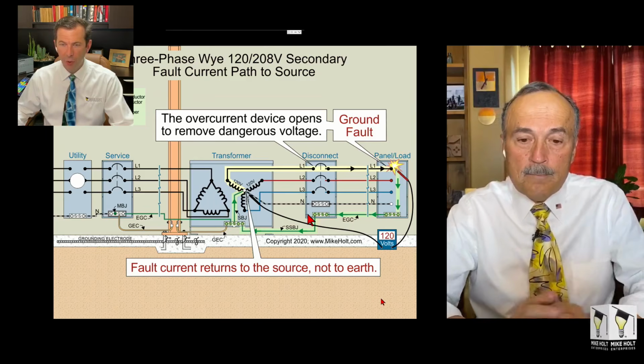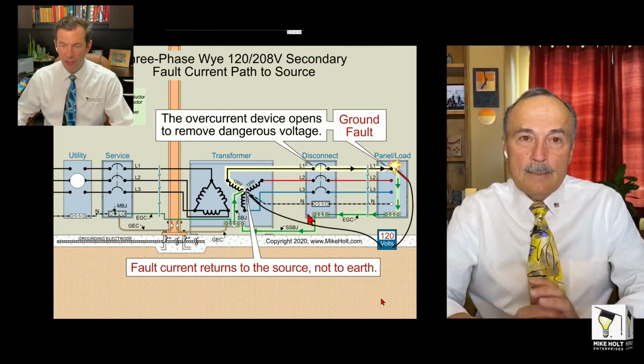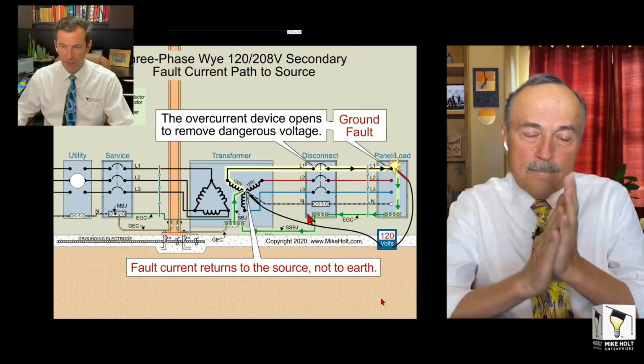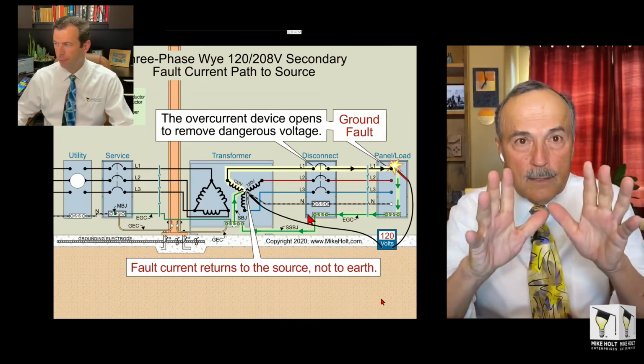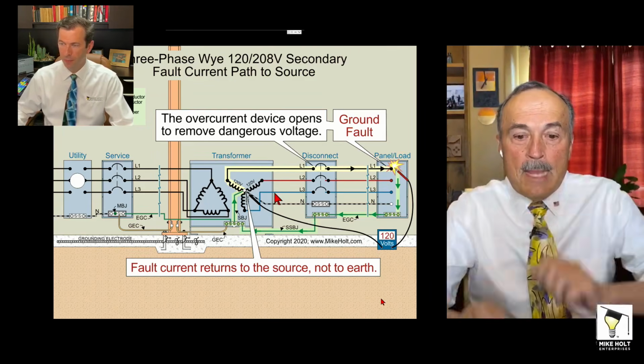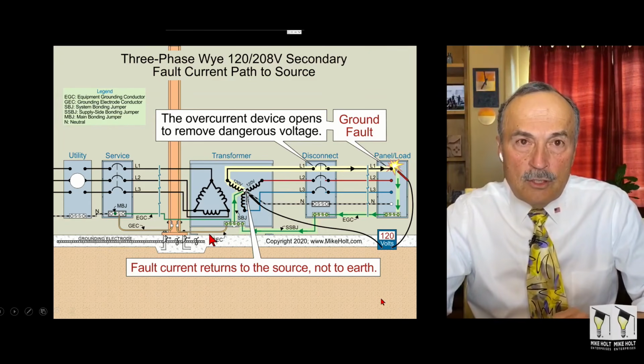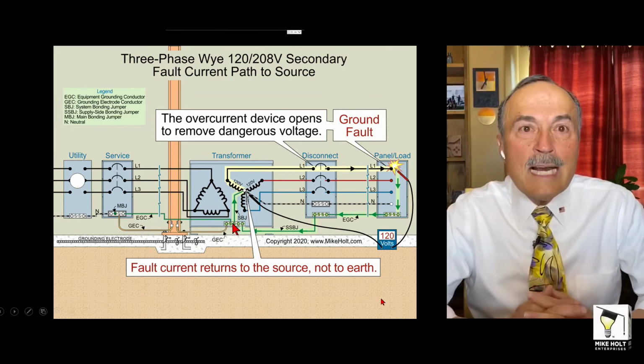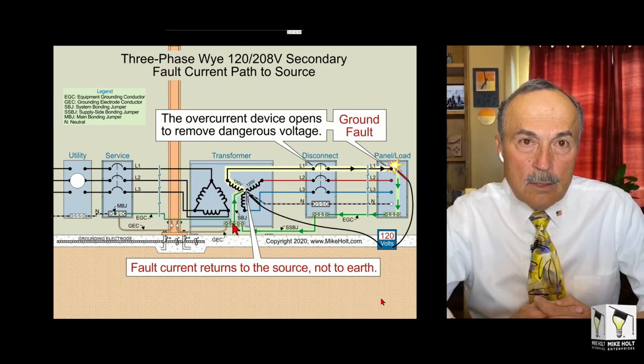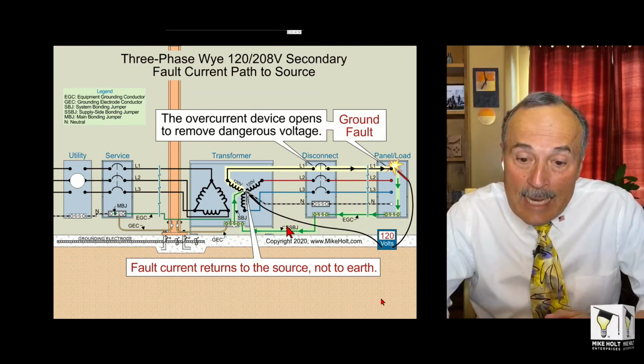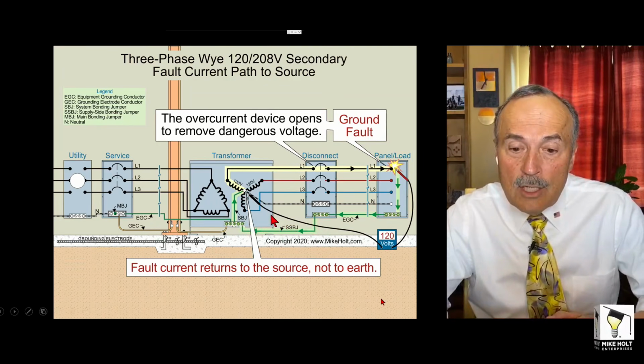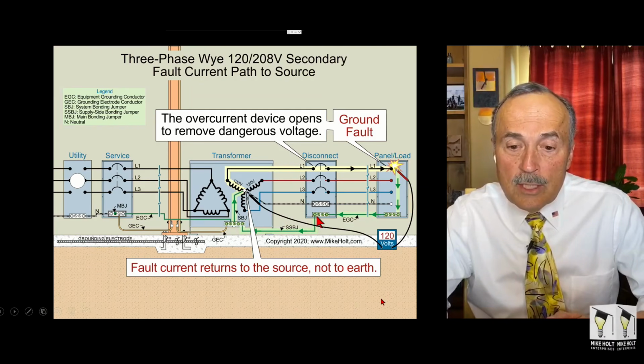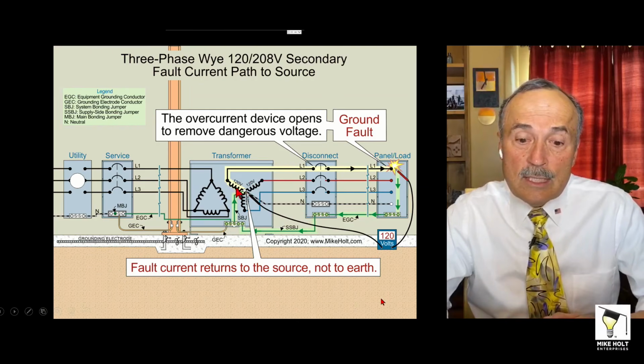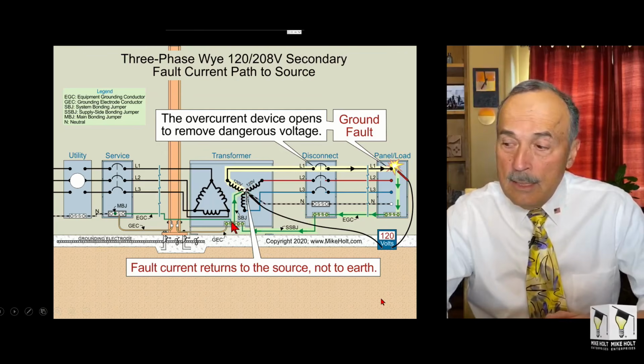I think where this is going is the issue, and you addressed this the other night with the bonding bushings. Guys, let me explain this. The system bonding jumper is where you terminate the grounding electrode conductor. The system, not your supply side bonding jumper. If you put a piece of metal conduit between these two here, that doesn't change your system bonding jumper.